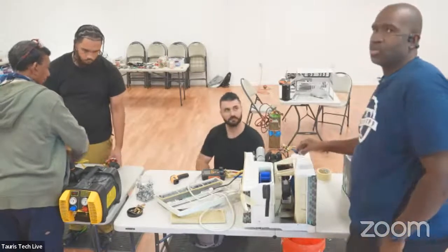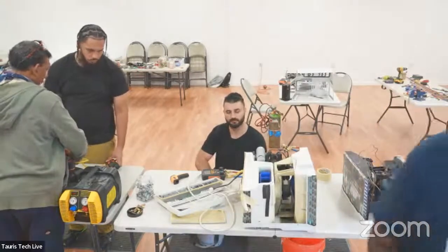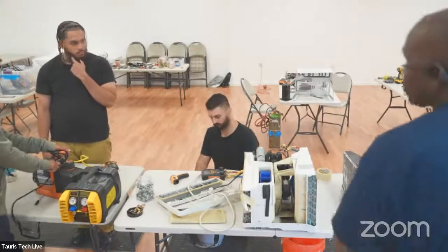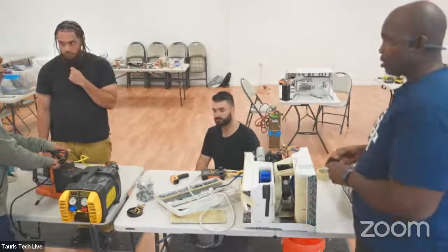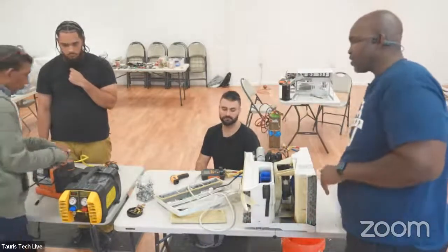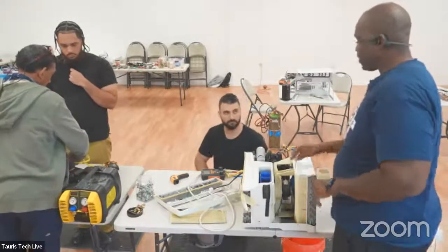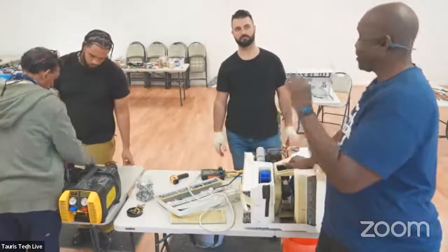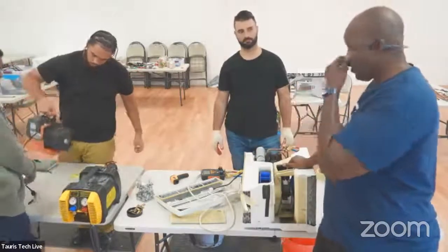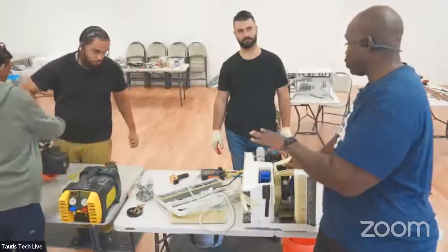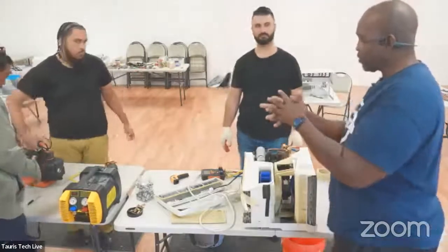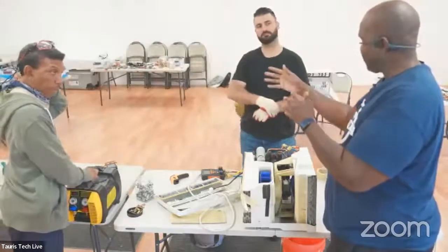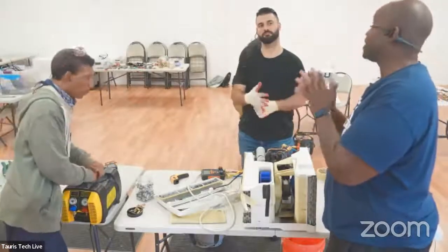With the older systems, if you had an R22 system, yeah, close. Otherwise you're just going to put air in there. With a system like R22, what they would do is charge liquid, the majority is liquid, and then they would top it off with vapor, so they could be sure they don't overcharge the machine. With this one, you always have to charge liquid because it's a blend. It's a mixture of two refrigerants. If you just try to charge vapor, you're only charging half. But if you want to have the full mixture, it has to be liquid.